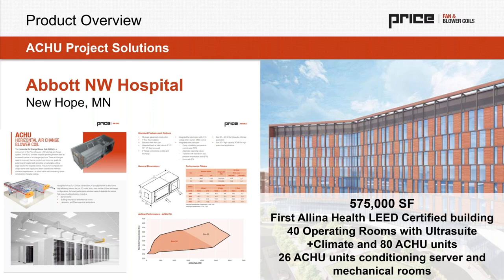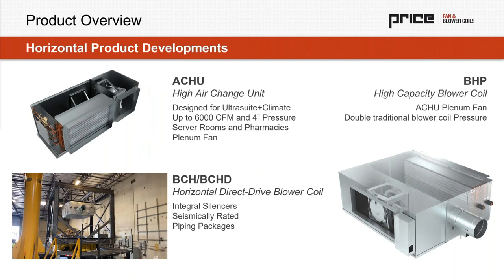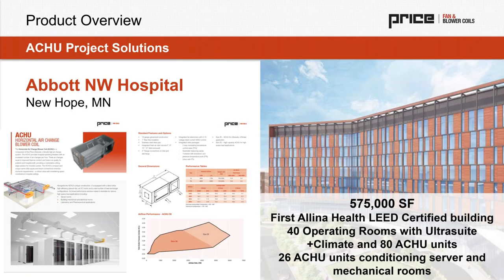A nice byproduct of this is it's actually a fantastic product with its 180 degree bend that we could see on the upper left hand side of this slide here. That 180 degree bend actually makes it a great solution as well for high sensible internal load spaces like compounding pharmacies and server rooms and things of that nature. And we've actually seen more applications for it for those requirements moving forward. So compounding pharmacies and server rooms being two really critical spaces that are often very duct constrained and ceiling constrained. So that 180 degree bend saves a lot of duct routing and therefore duct cost as well.